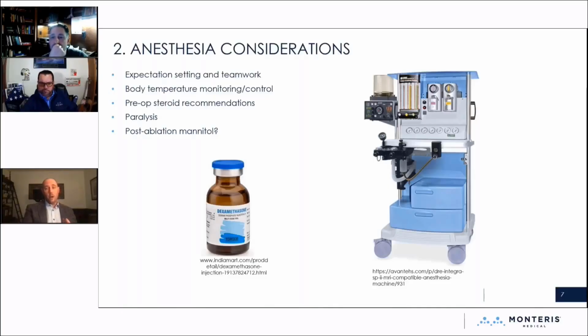Paralysis: the software has a trigger, and if you are ramping up to get ready to burn and something moves, the laser has an automatic shutdown. If it detects motion, it's a safety switch, a safety trigger, not surprisingly. Most of the time that there's movement, it's because the patient's not fully paralyzed. So make sure you talk to your anesthesia team about needing paralysis. I'm sure Monteris won't want me to say this too openly, but there are also ways to turn off that movement trigger, so you can do that if it becomes a constant issue. And you would talk to the person that's assisting you in the case.